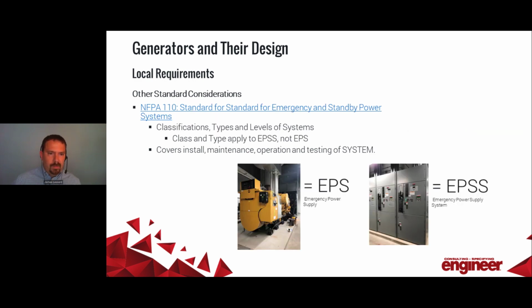NFPA 110, absolutely a staple when you're designing a generator system. It's the standard for emergency and standby power systems, and it introduces a few things, including classifications, types, and levels, which we'll get into in more detail in the next few slides. But it's important to understand what those are. Class and type apply to the emergency power supply system, which is the transfer switch equipment, and not necessarily the generator, which is referred to as the emergency power supply, or the EPS. NFPA 110 covers everything from installation, maintenance, operation, and testing of the entirety of the system. There's a lot of overlap between 110 and NEC and some of the other codes. So it's important to understand these standard requirements as well.